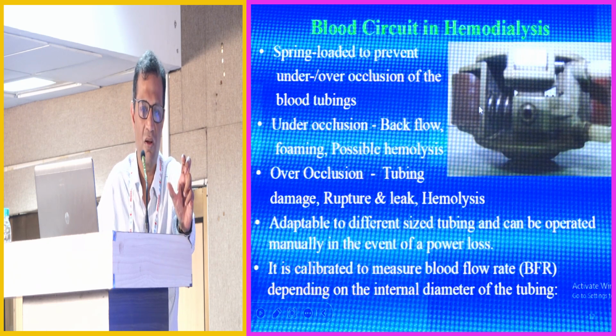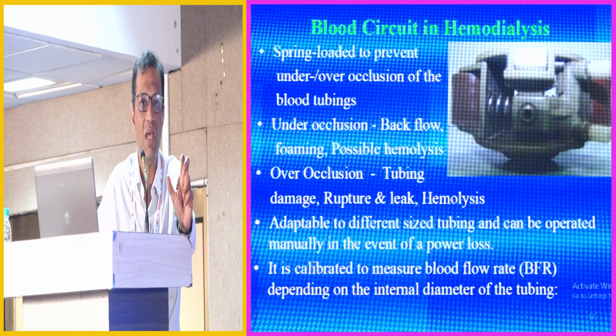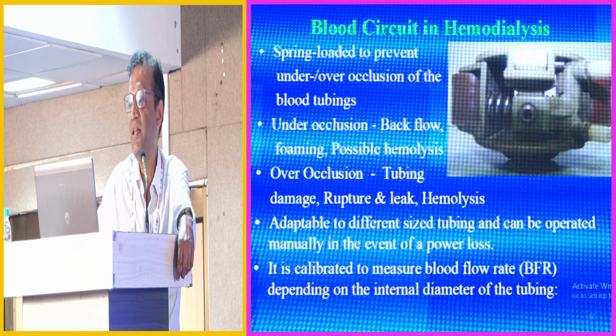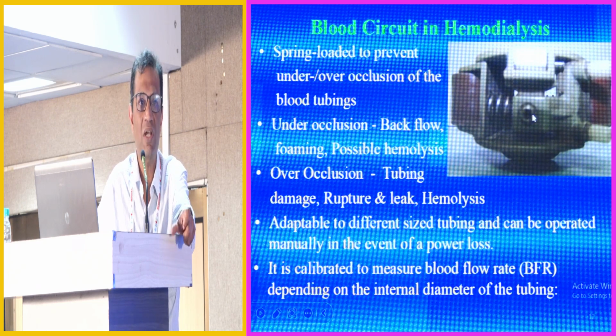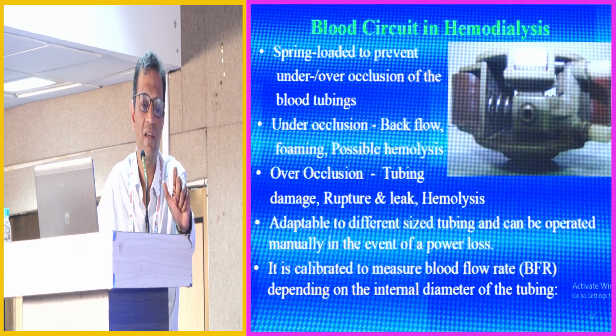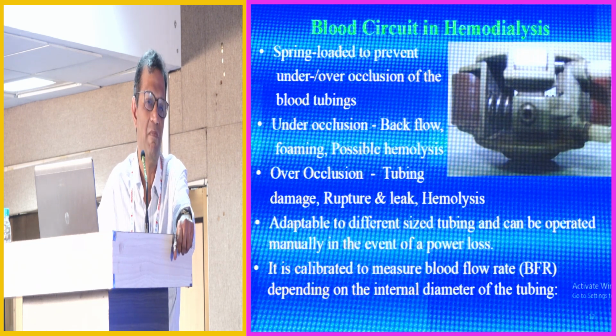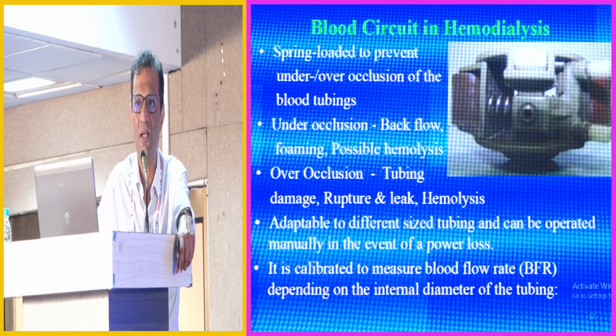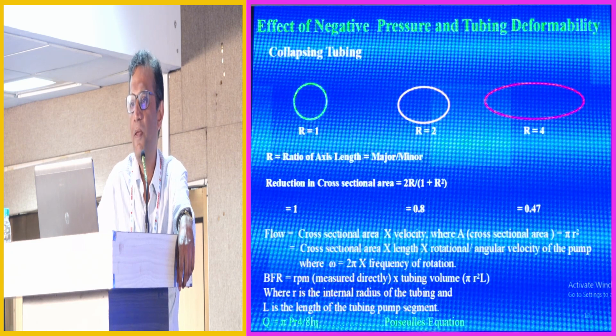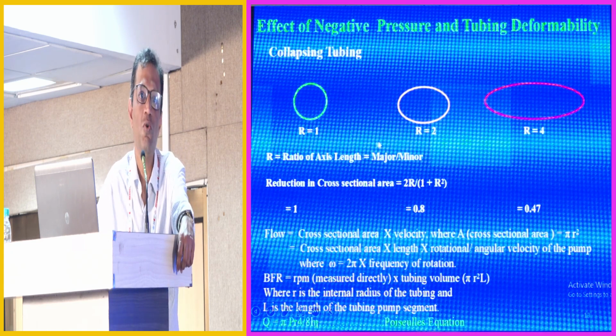So if the tubing set needs to be, the machine pump needs to be adjusted, the roller stator distance needs to be adjusted to the pump segment that we are using, and it can be done with the help of this nut here. If you tighten it, you increase the tension in the spring, and that pushes the rollers further apart, reducing the occlusion diameter. If you turn it anti-clockwise, it reduces the tension and brings the roller segments further, increasing the occlusion diameter. And failure to choose the right occlusion diameter can result in a lot of undesirable things, as you can see, to the blood. This is one of the things that happens when your occlusion diameter doesn't match.